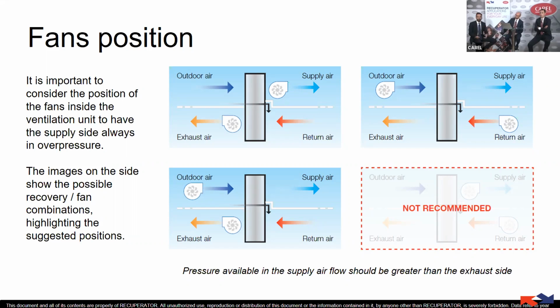And the fan position in, let's say, the not recommended one is where we have the fan on the building side, in the way we have the supply side under pressure. That is not good because the leakage is going to the supply side. That means cross-contamination. So what we suggest is to have the fans on the outdoor side, or the fans that are between the heat exchanger, as in the two pictures above.